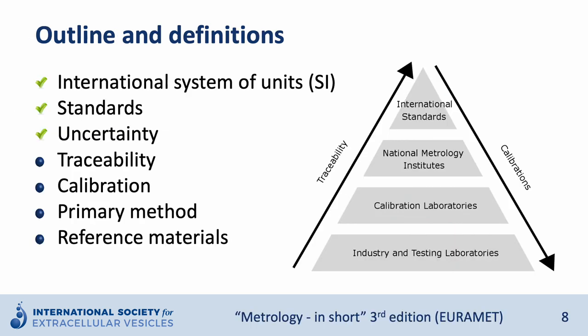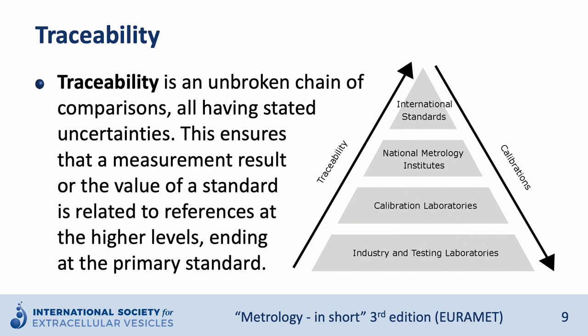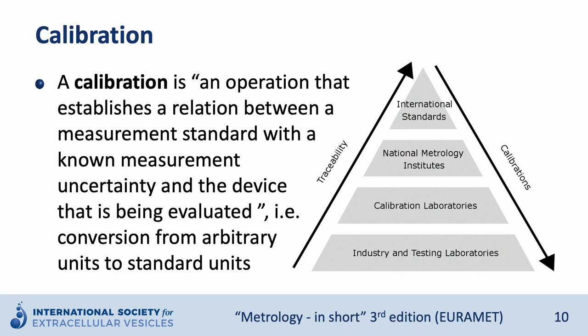In the following I will give the definitions of traceability and calibration which connect laboratories at different levels. Traceability is an unbroken chain of comparisons all having stated uncertainties. This ensures that the measurement result or the value of a standard is related to references at the higher levels, ending at the primary standard. Calibration is defined as an operation that establishes a relation between a measurement standard with a known measurement uncertainty and a device that is being evaluated — for example, conversion from arbitrary units to standard units, which is very important in the EV field.